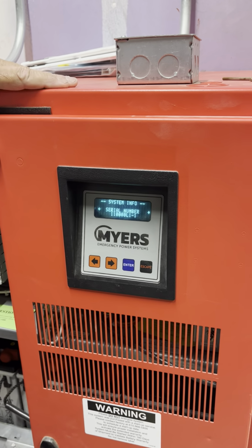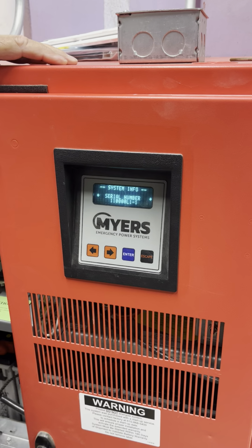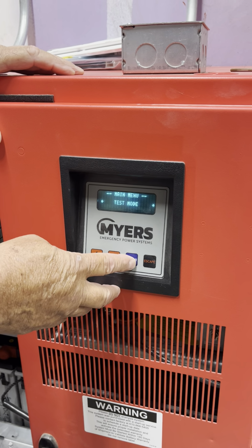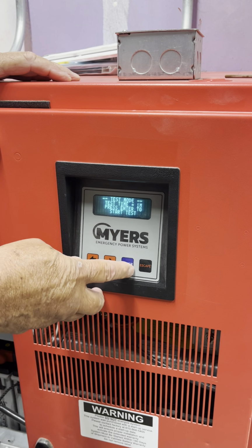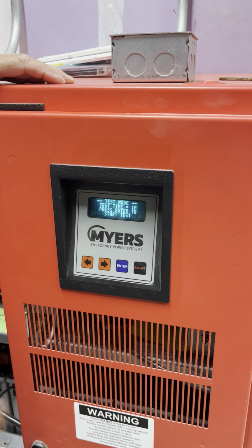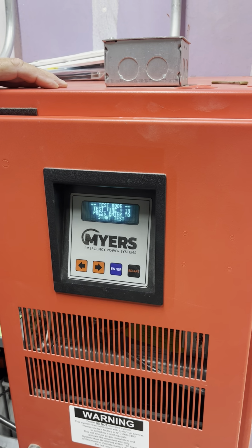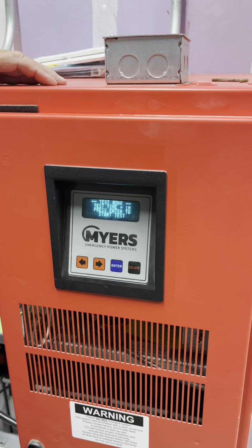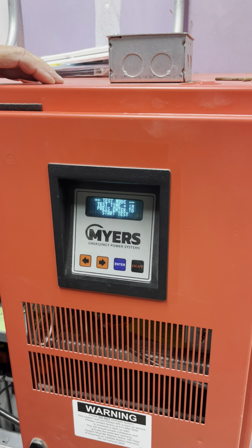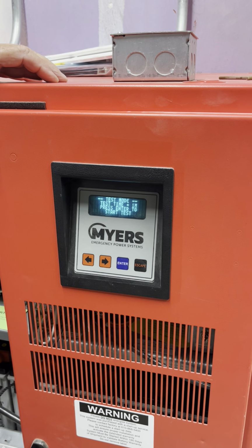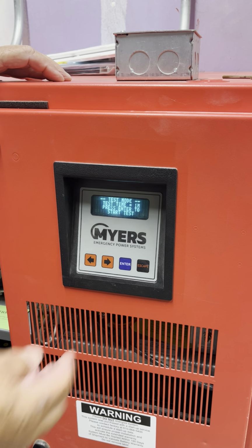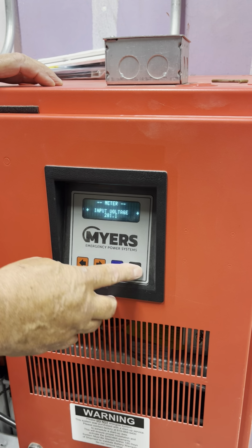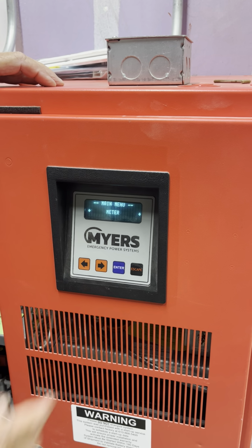Sometimes the keys get lost. Some people don't like their hands in here, so you can also get it right there. Okay. Test mode, if you want to run a 1-minute test without turning anything off, you go here to do it. Hit the last key, hit enter one more time, hit enter. And it does a 1-minute test. Test runs actually about 30 to 40 seconds, but its whole process is a minute. If it had an issue during this little test, it would come back out and give you an alarm. Okay. You can still access everything from here. All your metering, everything is still accessible while your test is being run.